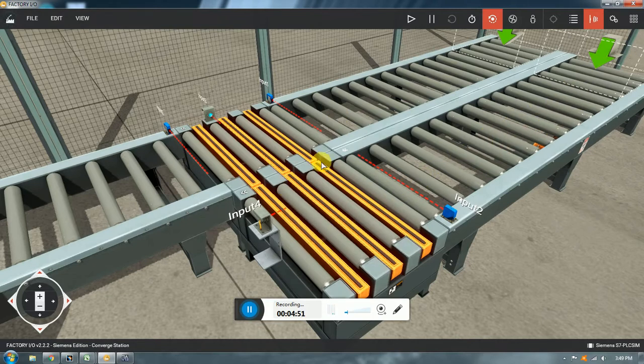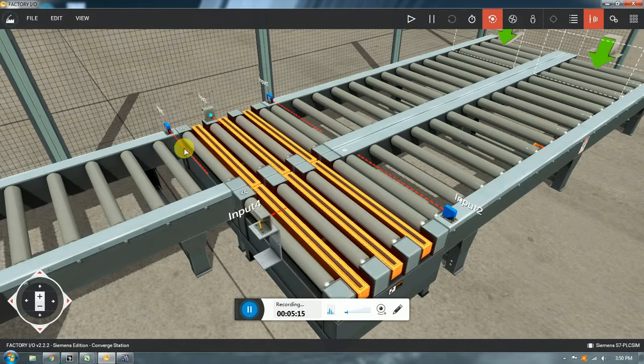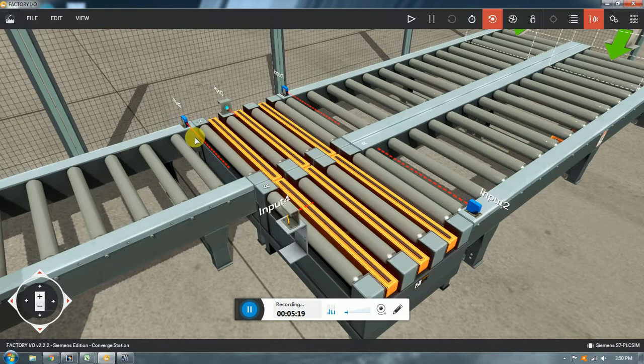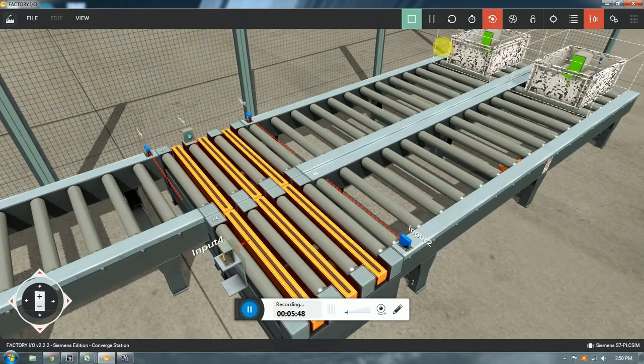The sensors are going to determine if there is a container in this area, or in this area, or if it's before or after. The separation between the capacitive sensor and the diffuse sensors — both here and here — should be less than the length of the container. So if a container is between input one and input five, it is going to be detected by at least one of those sensors. That's really important because I don't want a blind spot where the container may be hidden from the sensors and the PLC tells the system to do something too late.